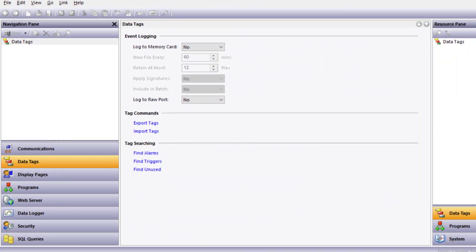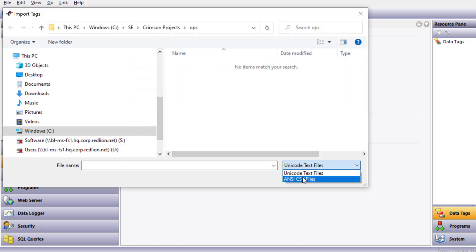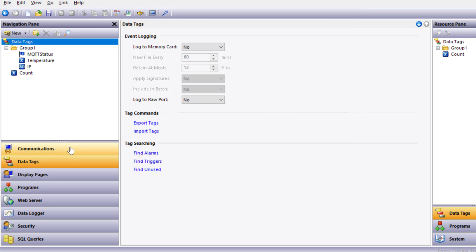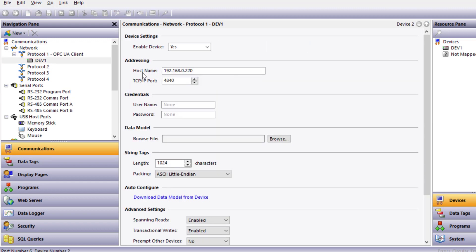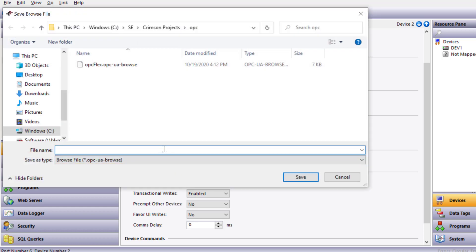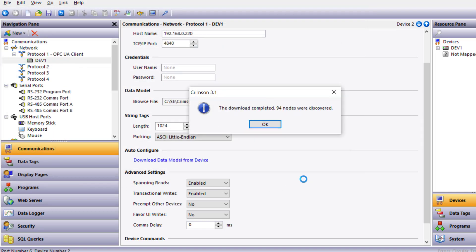I want to show how easy it is to set up a Red Lion device using OPC UA client to pull the data tags from a Red Lion OPC UA server. First, I'll import the tag file from the OPC UA server project file. I've already exported tags from the server, so I'm going to select Import, CSV file, and select the FlexEdge server tags. Next, I want to go to Communications, Protocol, and pick OPC UA client. I've pre-configured the host name, which is the IP address of the server. Scrolling down, you'll see the AutoConfig feature — download data model from device. Since my laptop is networked to the OPC UA server, I'm going to hit Go, call this FlexServerTags, and select Download.